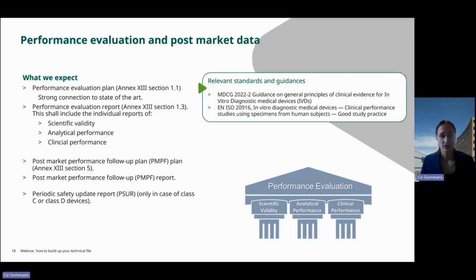Then for the post-market part, during the technical file review, we look at the post-market performance follow-up plan, which is described in Annex 13, and if applicable, the post-market performance follow-up report, only if applicable. The PSUR, it's good to mention here that the PSUR is only for class C and D devices, but also after the device has been certified.